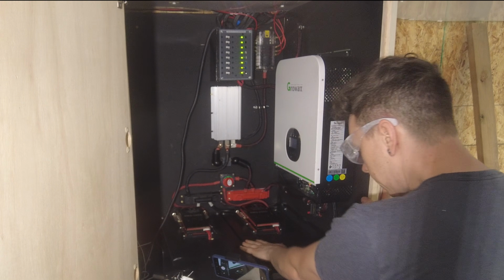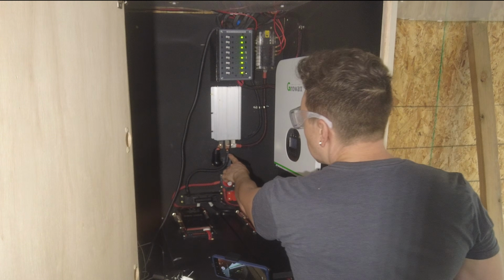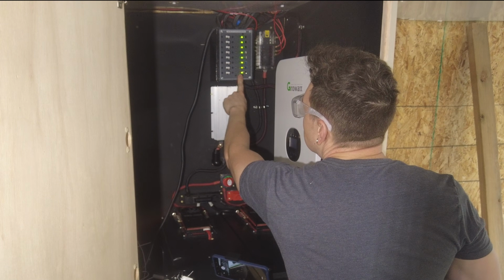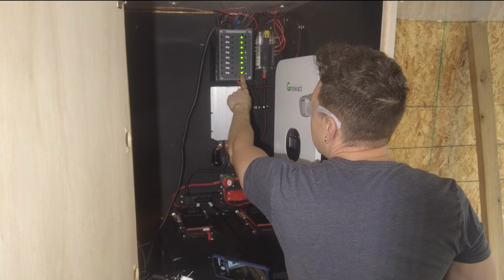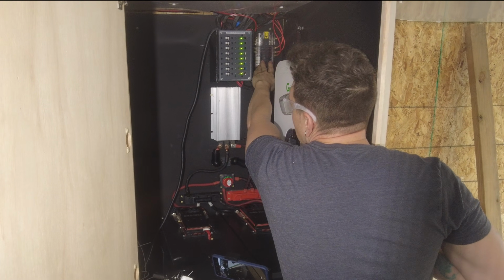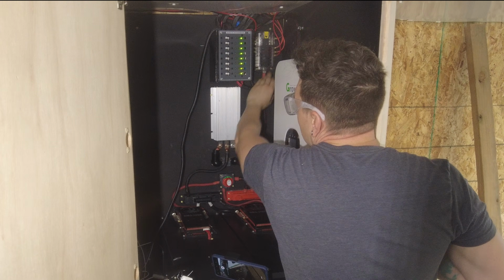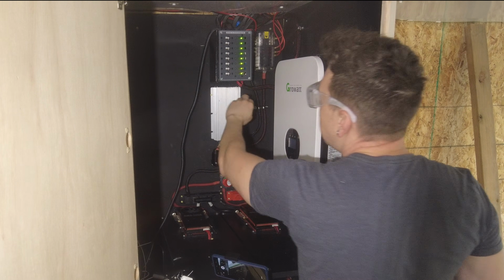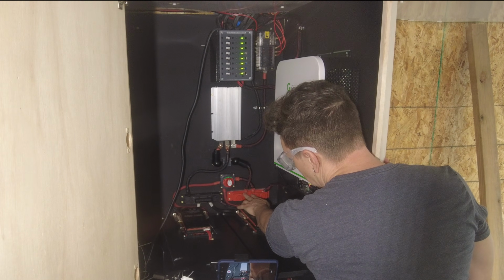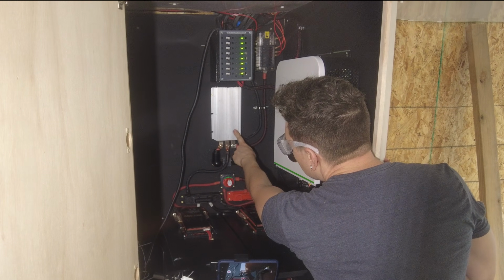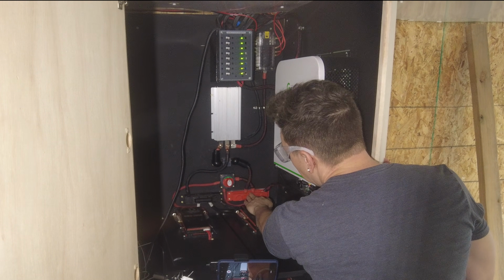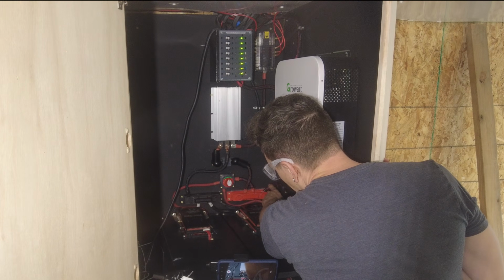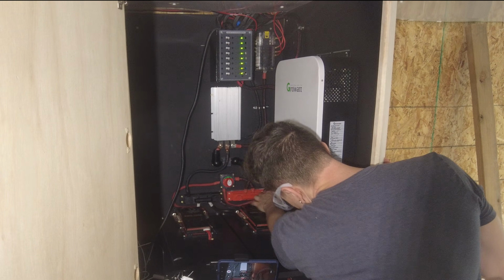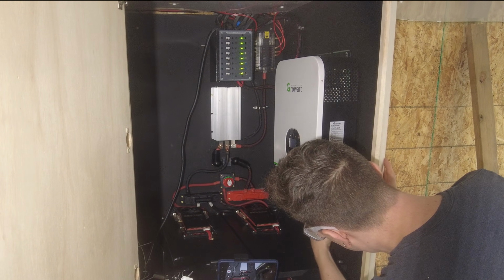This is on and open, which means we've got power coming from the batteries. We can see this is on, which means we have the 12 volt. These lights are powered by 12 volt, which means this breaker is indeed working. We have power from the 24 volt to the 12 volt step down. We know we have power at the bus bar, because to get to the 24 volt to 12 volt step down, it has to go through the bus bar. So we have power here. We just don't have power getting up to here.